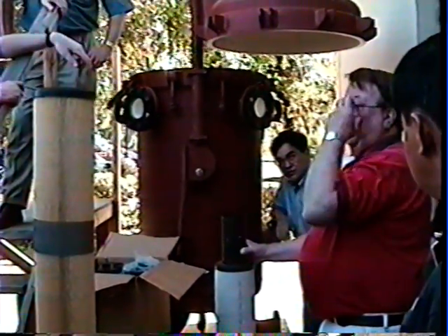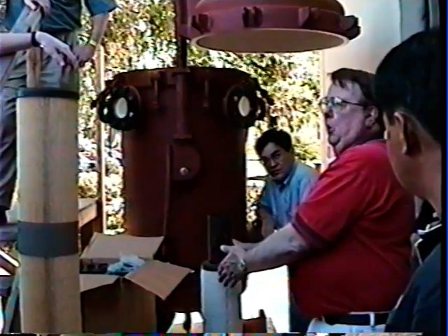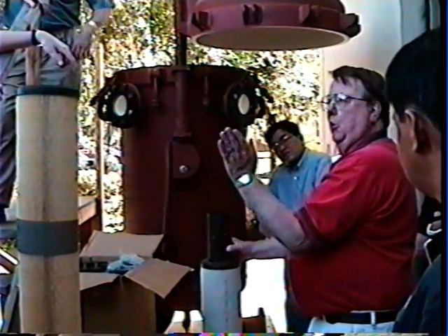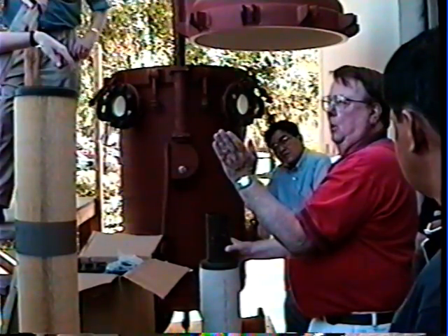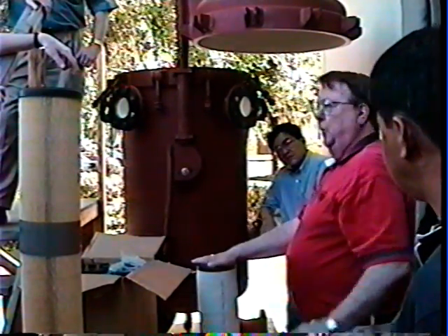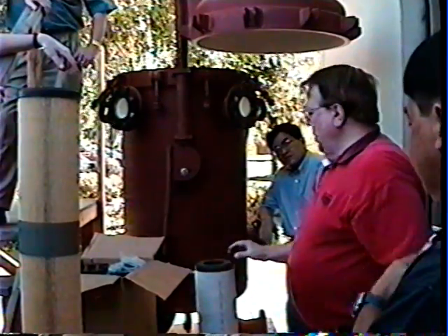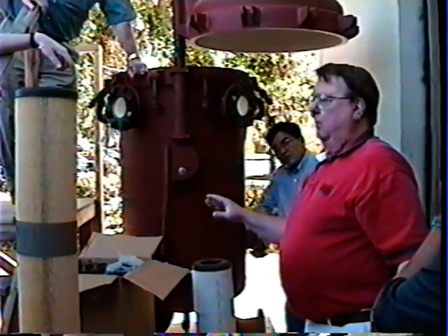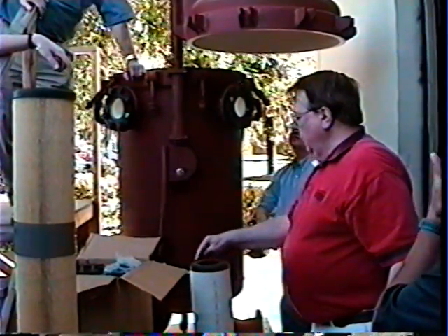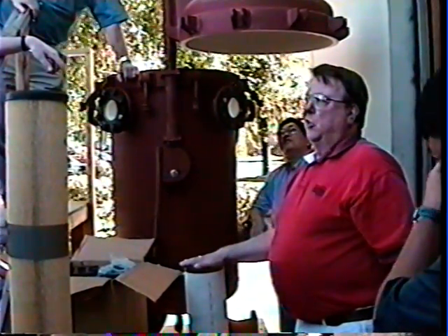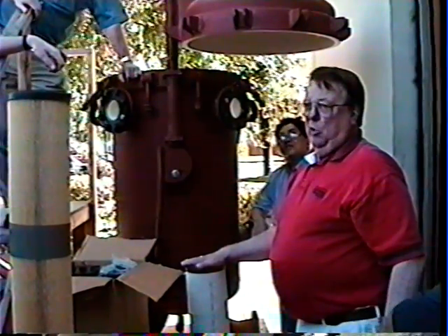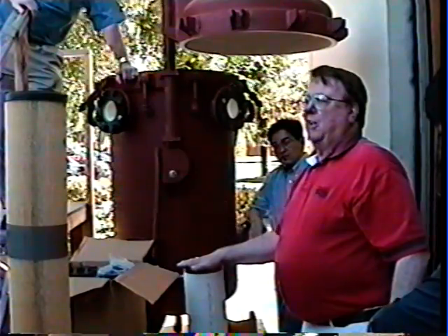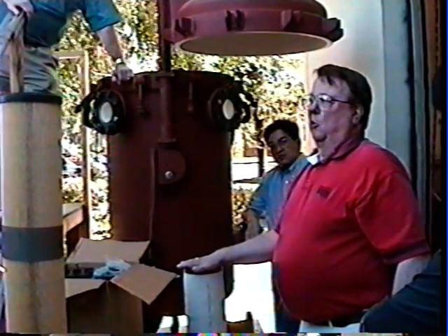And how they'll see it is on the delta P gauge. Normally they change this element every month. Now they're going 5 weeks, 6 weeks, and the delta P is not coming up. Then they know they have a problem with the seal. So what you can do, if they're seeing a problem with real extended life, is to pull the elements out and always check your seals, top and bottom, to make sure that our spider left a round imprint in the middle of the gasket seal. Okay?